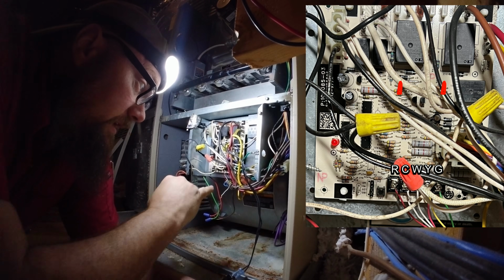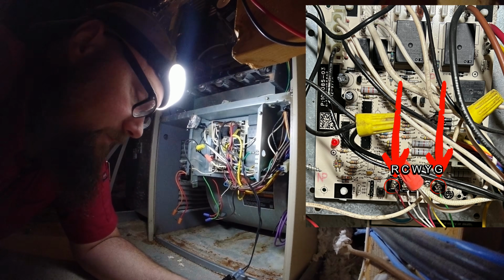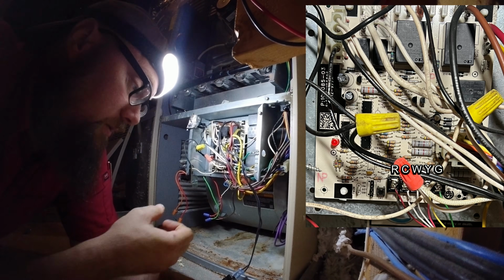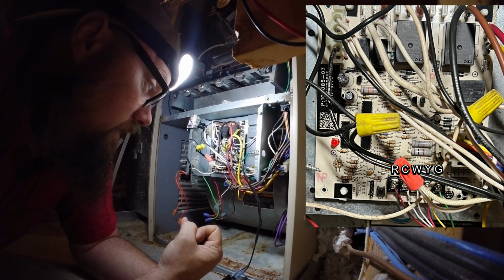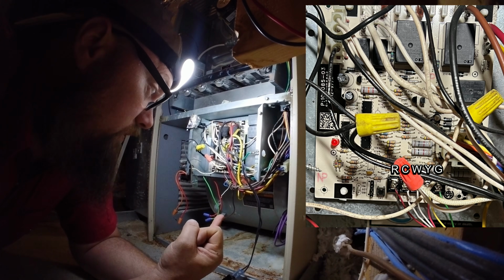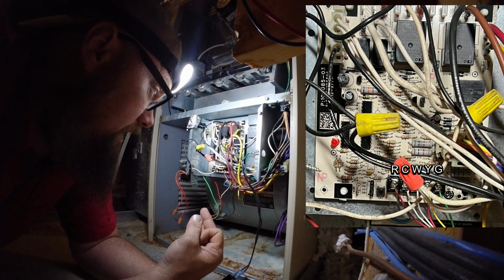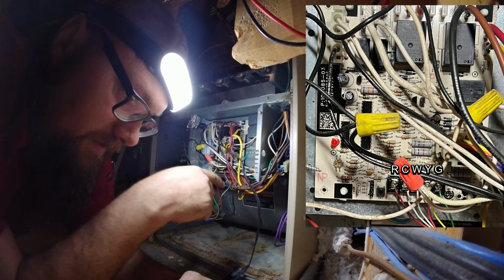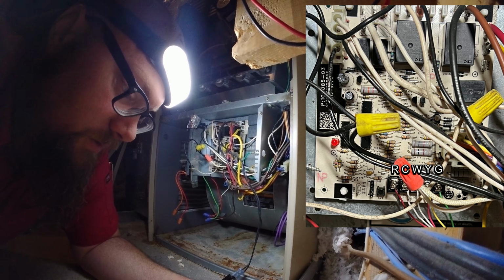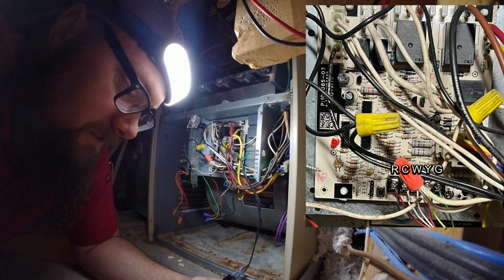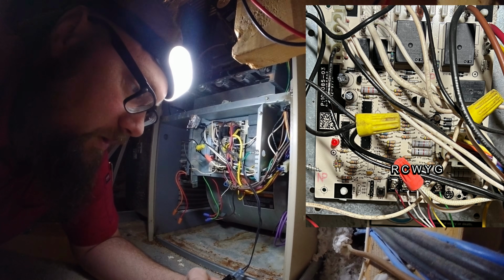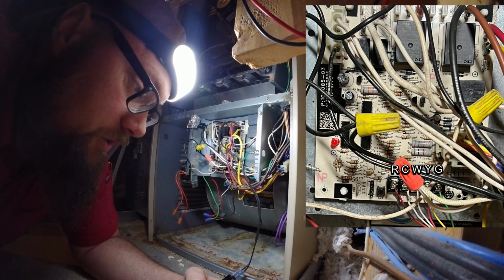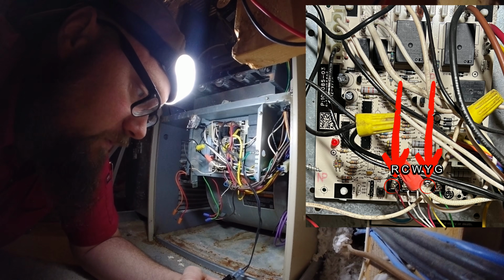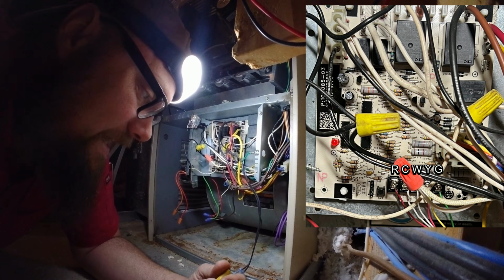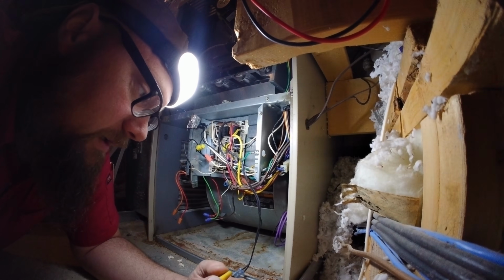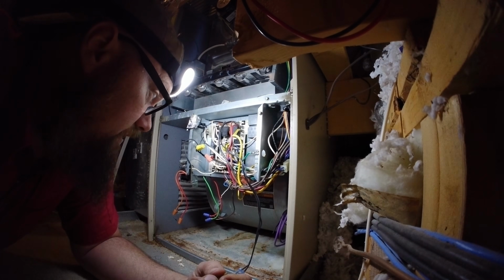Then we're going to jump between the red and green to see if it's shutting down due to a short somewhere there. We know thermostat seems okay in heating mode. Zone board seems okay in heating mode. Did not really have an issue with that. So we'll jump between red and green once this shuts down, see if there's possibly an issue with the fan motor relay itself or thermostat zone board calling for fan. And if that doesn't give us an issue, we'll jump between red 24 volts and the outdoor unit HVAC and see if we have an issue there. And that way it will at least point us which direction we need to go.